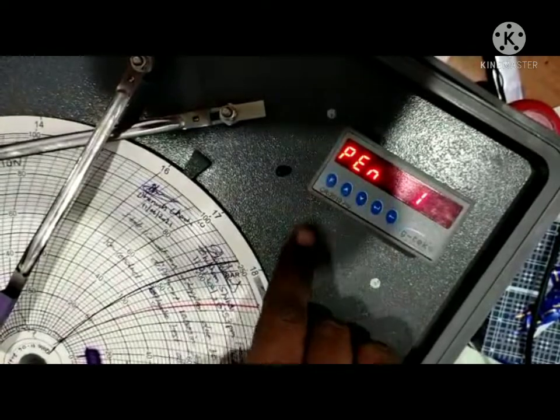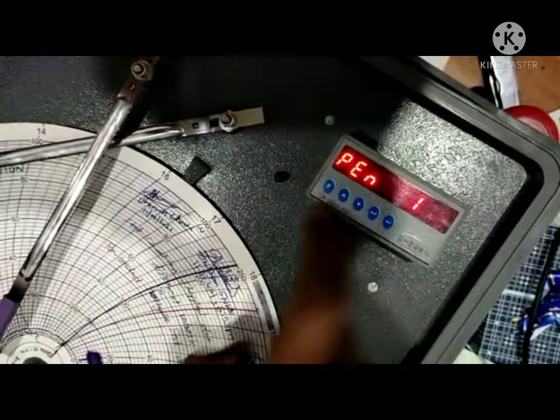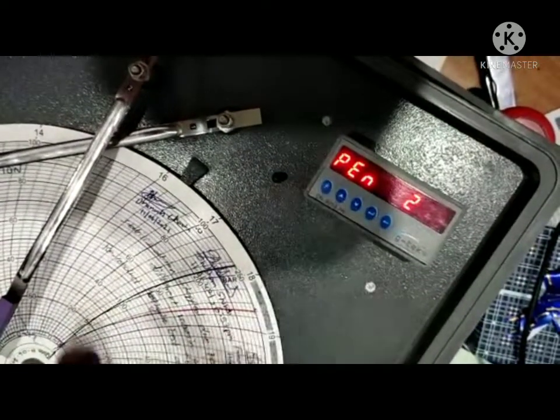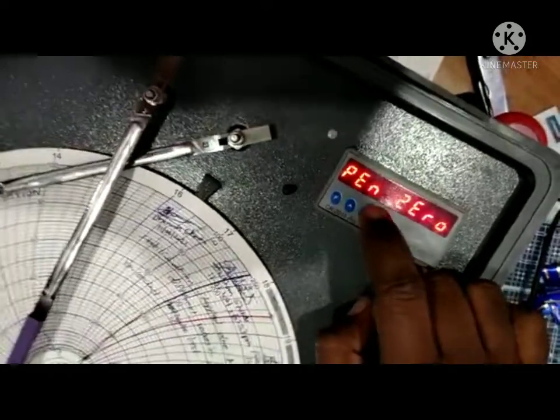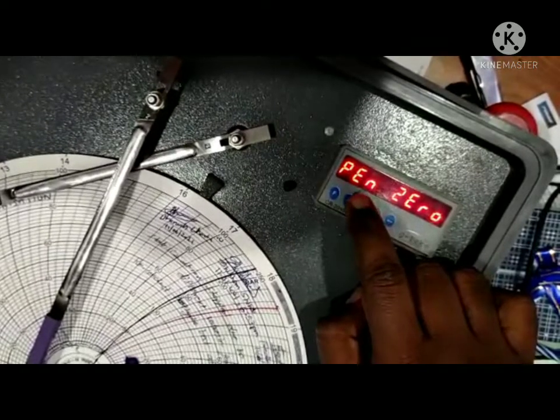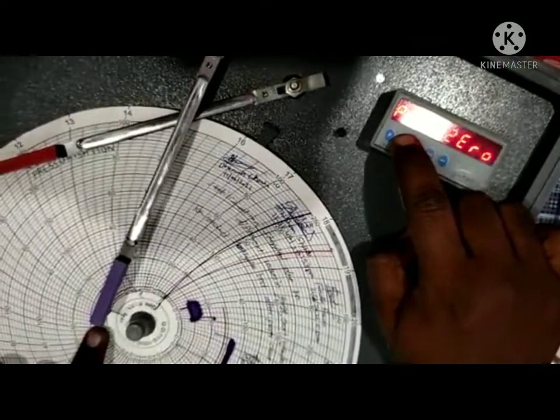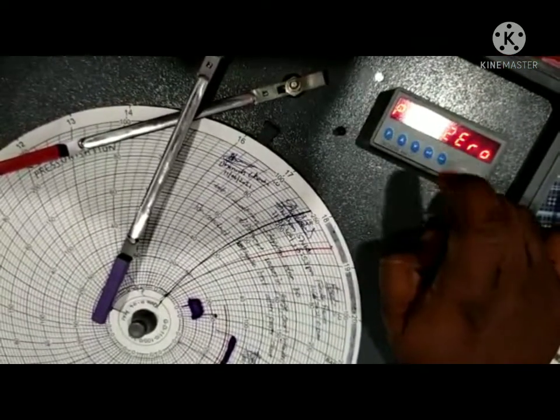Press Enter and select the required pen. Press Enter to start the calibration. Now the pen will move to the zero position. You can check the pen tip is aligned with the zero and you can make adjustments using the up and down keys.